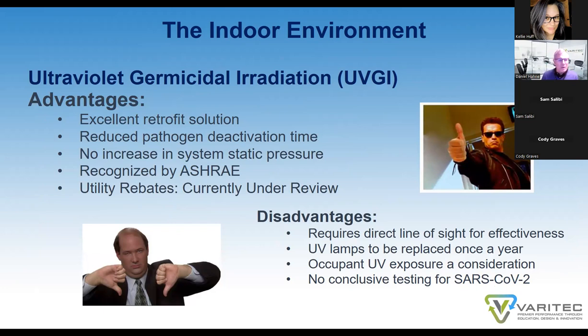They can actually increase, there's no increase to system static pressure, which heightened filtration otherwise does, causing an energy burden. They are recognized by ASHRAE, and during the pandemic there were rebates being offered for this technology by certain utility companies. The disadvantages of UV light are they require a direct line of sight for effectiveness. UV lamps need to be replaced once a year, so there's a maintenance cost associated with them. Occupant UV exposure needs to be considered, and proper notices put on air handlers using the technology to make sure that those lights are disabled when a service tech is opening an air handler door, etc.